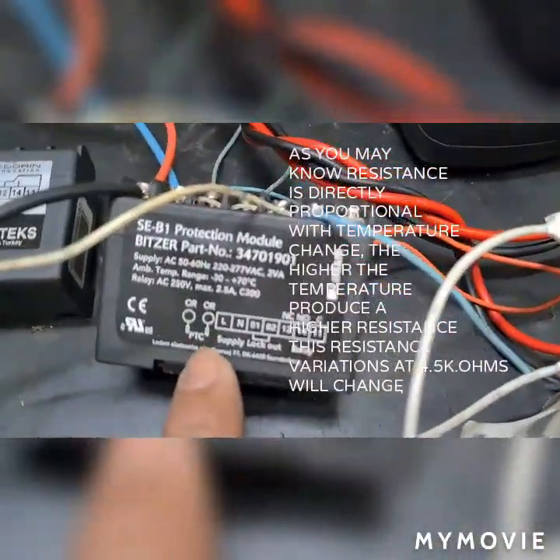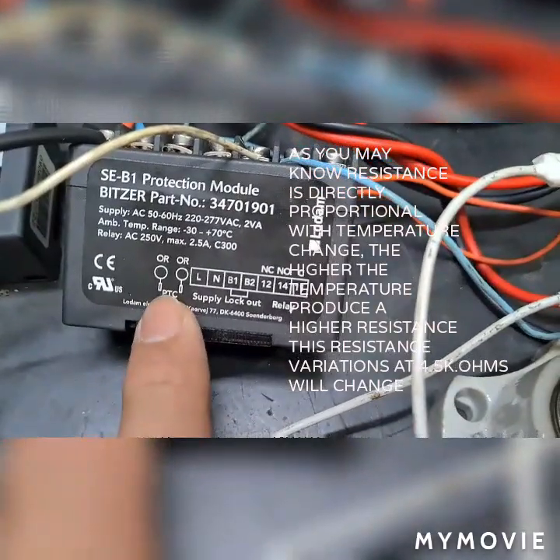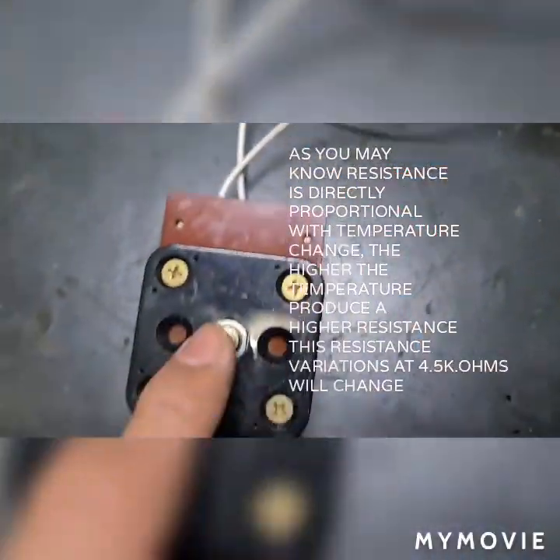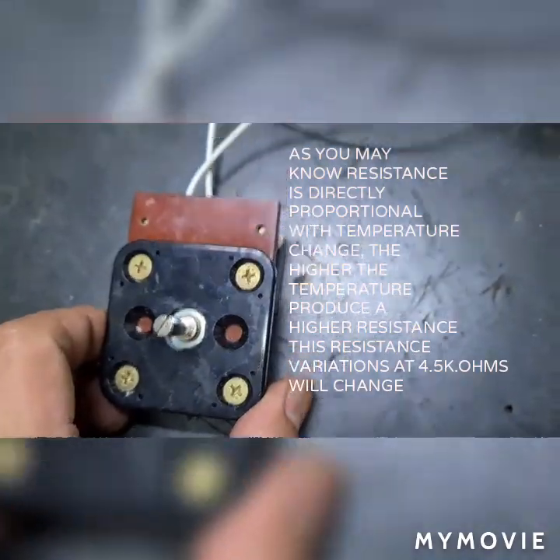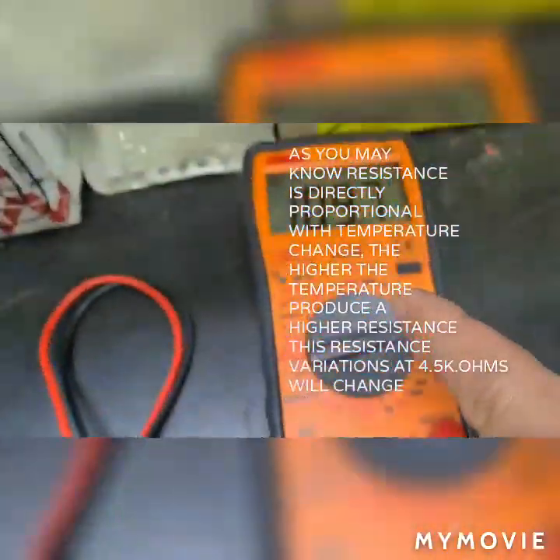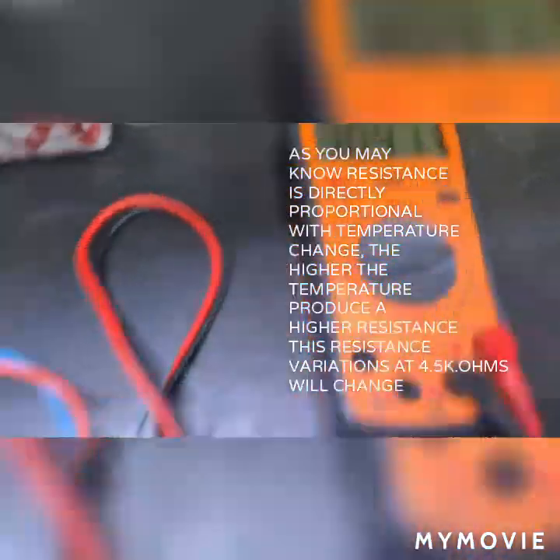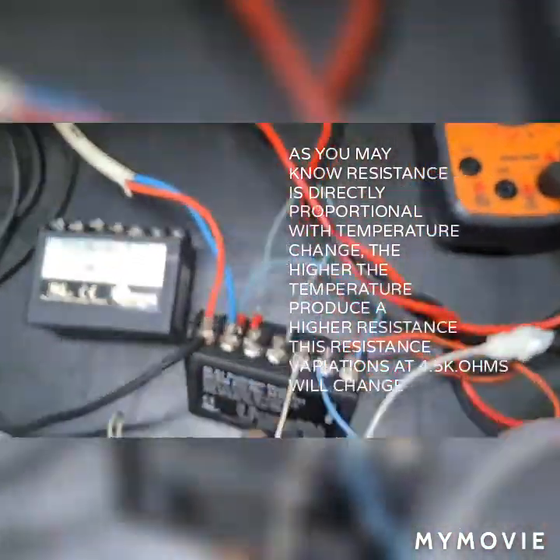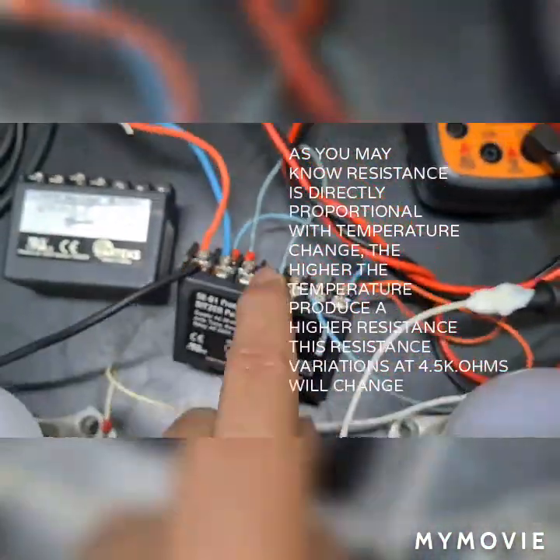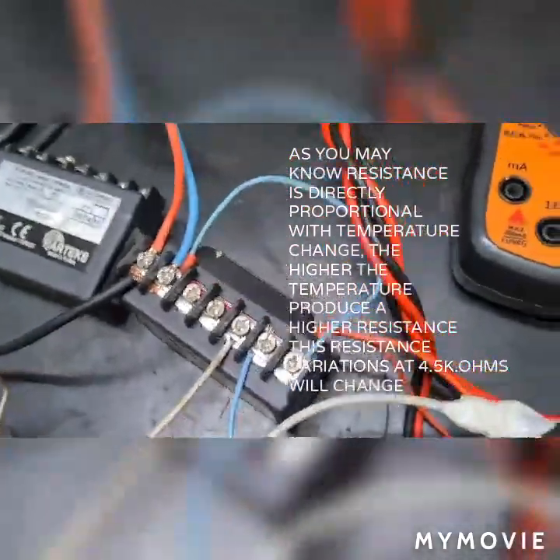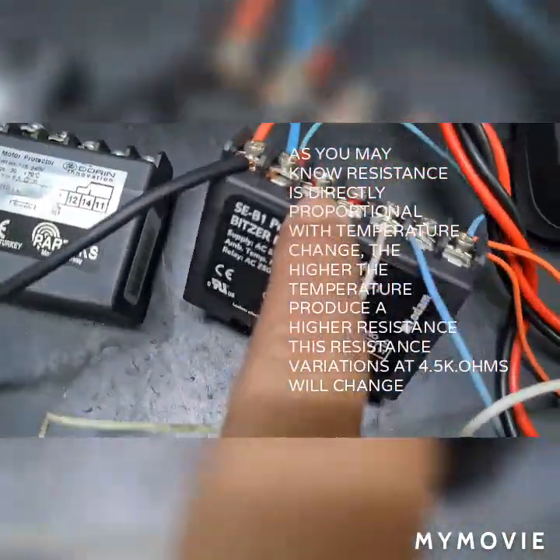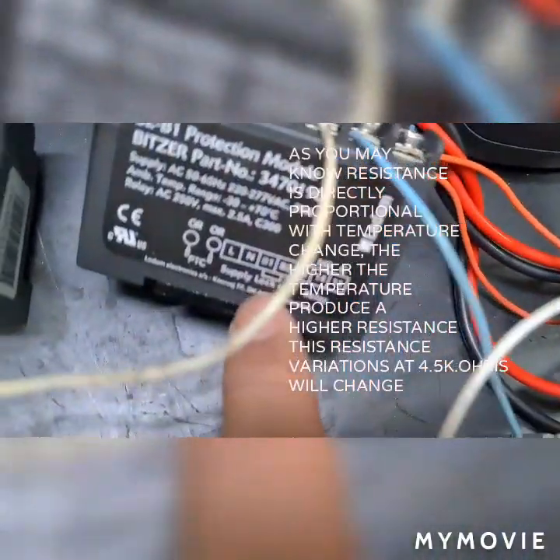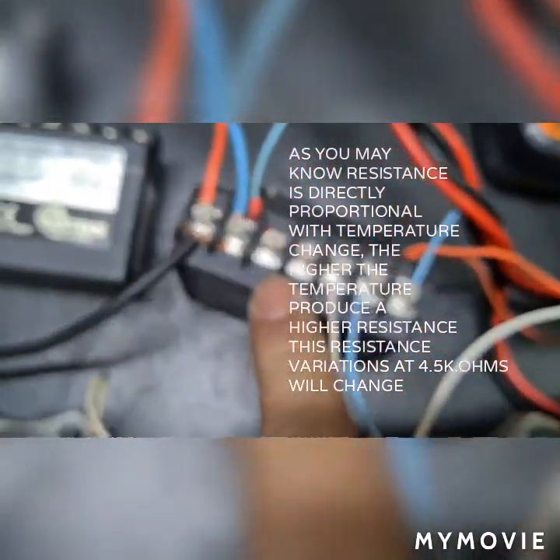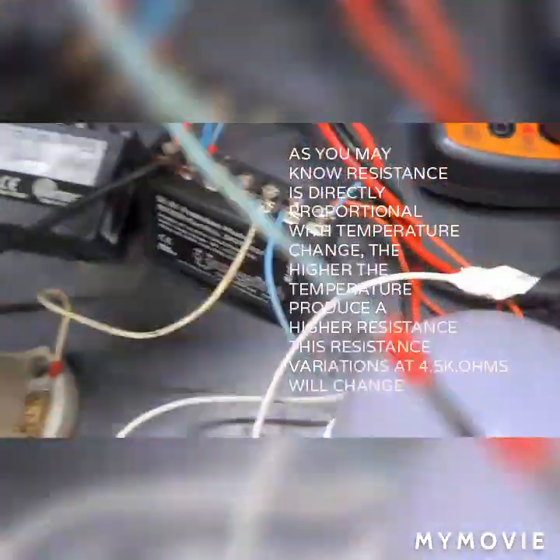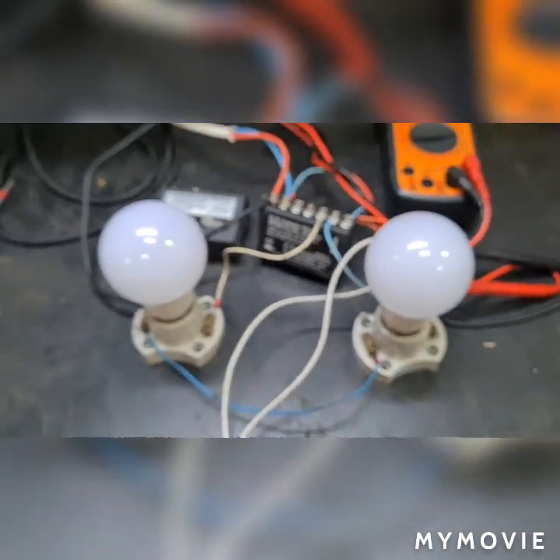So what I did now is I put a potentiometer on the orange cable wire, having 109 ohms, on my PTC, and I connected the supply L and N with 230 volts, and I just removed the lockout connection on B1 and B2. Then I connected the bulb on the left on the normally closed contact, terminals 11 and 12, and the other bulb on the right side on terminals 11 and 14, which is normally open. So having a resistance of 109, the 11 and 12 contact is closed, so I have light on the left side.